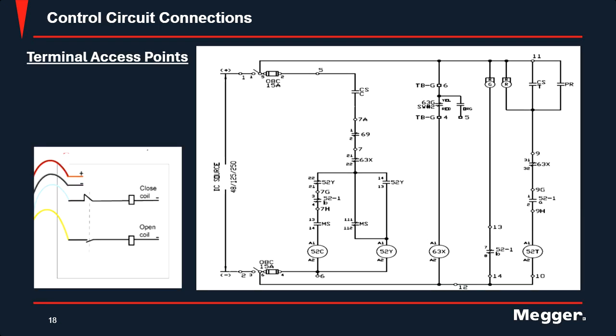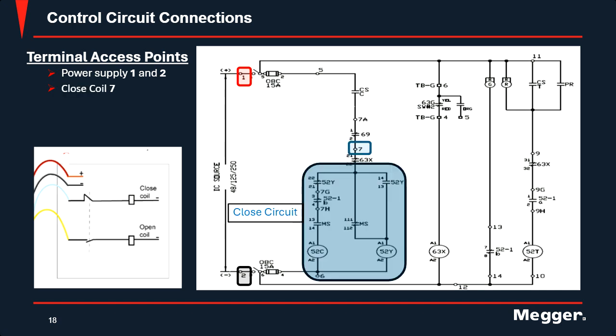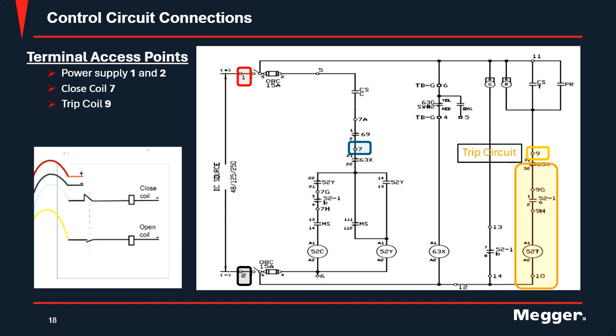So getting more into that, as I said, the first connection is going to be your control circuit. You have your terminal access points, and you should have a drawing for that medium voltage control power circuit. The first thing you're going to hook up will be your power supply. Based off this drawing, it's going to be on node 1 and 2, as I have selected there. Then you're going to do your close coil. In this case, it's node 7, in line with your close circuit. And then you're going to do your trip coil or open coil, and that's going to go to node 9. That's in line with the trip circuit.